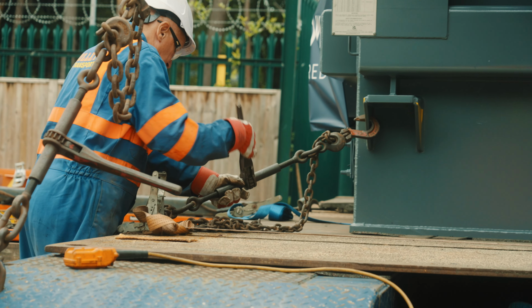The existing substation here has two transformers, which is there for redundancy. So in the event of a fault or maintenance, we can keep all the supplies on with the other transformer. When we are replacing these transformers, we will always have one in service, so customers will see no interruption in their supply whatsoever. And on completion of the project, we'll have two transformers back into service.